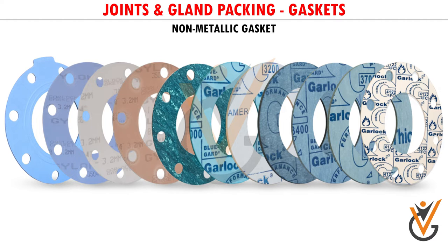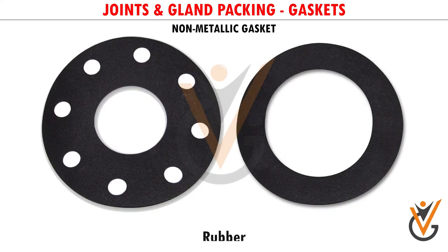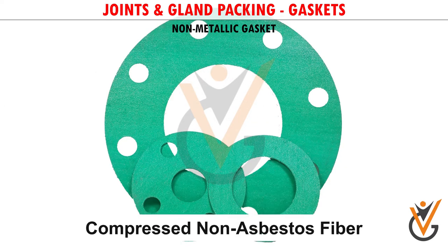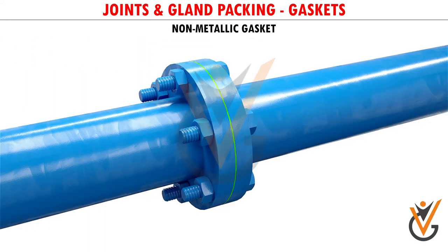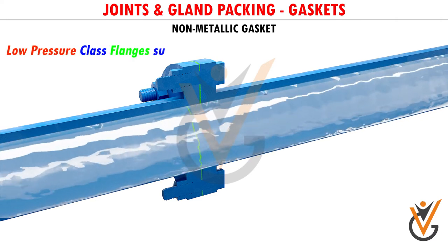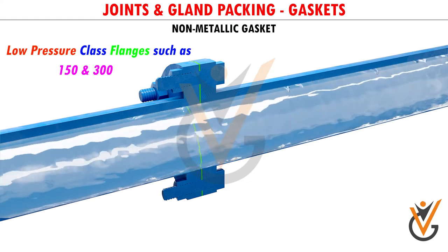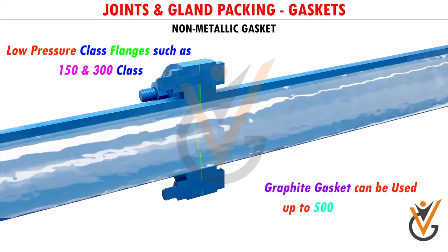Non-metallic gaskets. The most common materials used for this type of gasket are graphite, rubber, PTFE, and compressed non-asbestos fiber. These gaskets are also known as soft gaskets. Non-metallic gaskets can easily compress with low tension bolting. They are used with low pressure class flanges such as 150 and 300 class, and also in low temperature. However, graphite gaskets can be used up to 500 degrees centigrade.